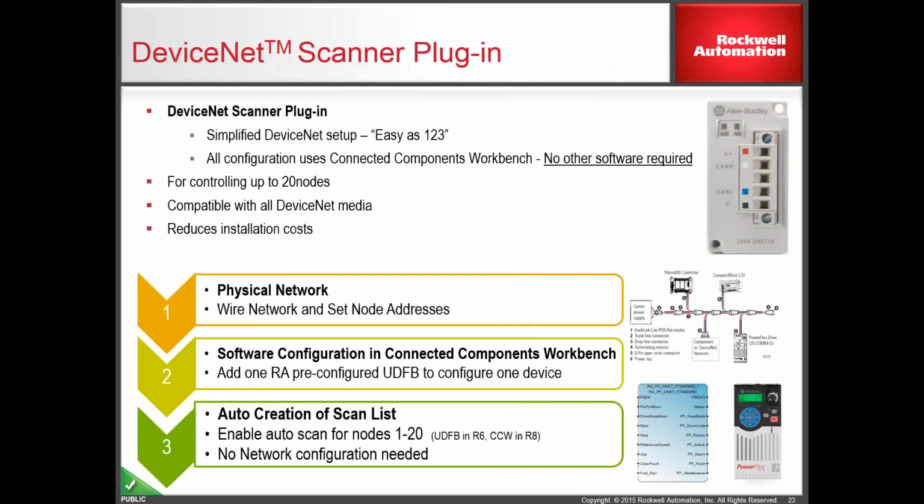So this is a DeviceNet Scanner plugin. As I said, it is required if you would like to go for a remote I/O configuration. It can support up to 20 nodes. So you can put 20 drives, and then you can put remote I/Os. We have 300 I/Os in remote, which is tested and validated on this configuration.